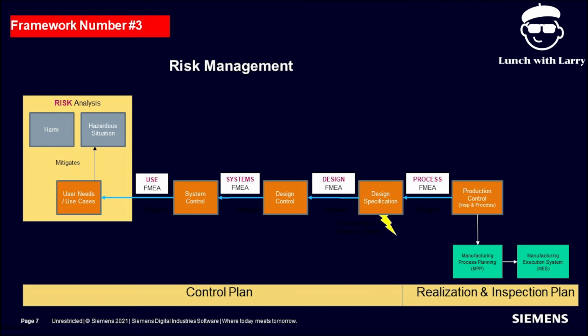Okay, so we do a systems FMEA that looks at the system control. Now we build out the design controls. An example of this might be that the sterile barrier bag doesn't migrate bacteria. Then we would process the design control of non-migration of bacteria using a design failure mode analysis and come up with a set of design specifications to assure that our design performance is built in a way that controls that design control. So the design specifications might be things like a sterile barrier bag with Tyvek, using Tyvek for the gas migration, and we might have a 3/8 inch bag seal as an example.